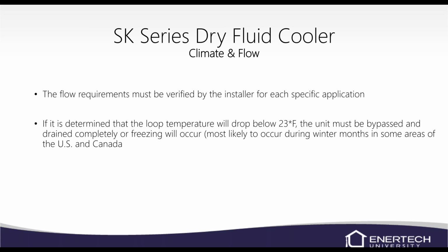Flow requirements must be verified by the installer for each application. We don't really know what size loop field you're putting it on, how much piping you've got to run. So make sure you're installing pressure temperature ports. That's really the only way we're going to find out how much water flow we're moving, is pressure drop. So make sure we're putting PT ports in, and always check the flow when we start the unit up.